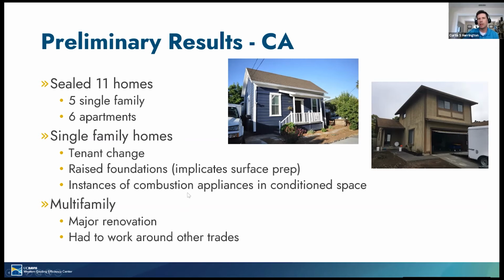You need to be aware of combustion appliances in the house, not stoves so much, but water heaters or furnaces in the conditioned space. When you seal buildings and have exhaust ventilation for the kitchen or bathroom, if those fans turn on and you have decent depressurization because of a tight envelope, you can create a combustion safety problem if there isn't adequate makeup air. So we have to pay attention to these things in existing buildings, along with considering ventilation in older homes that may not have it when sealing them up.